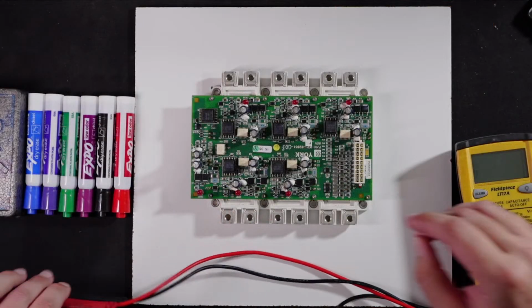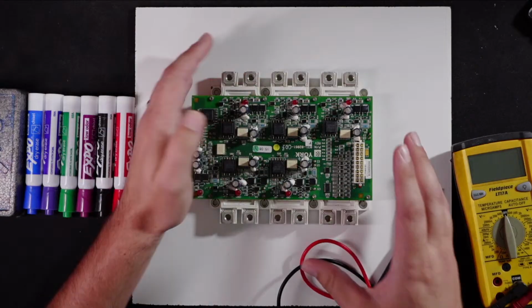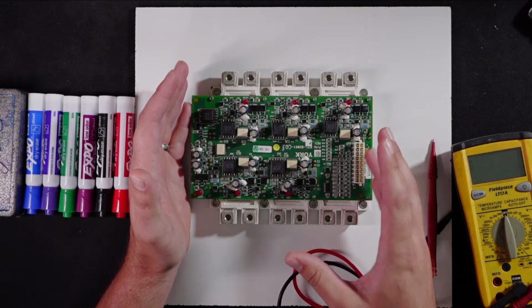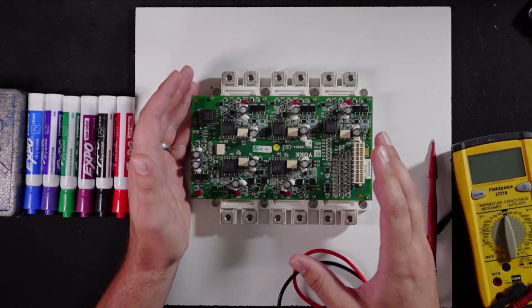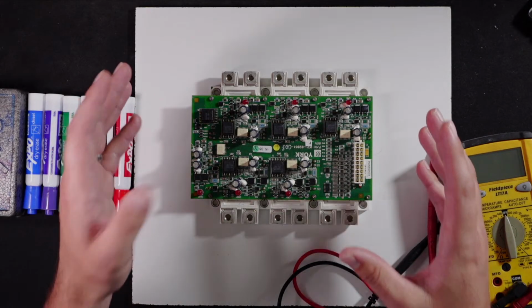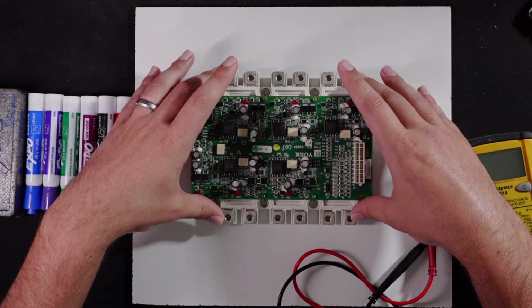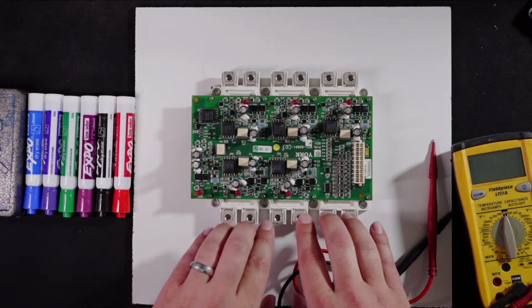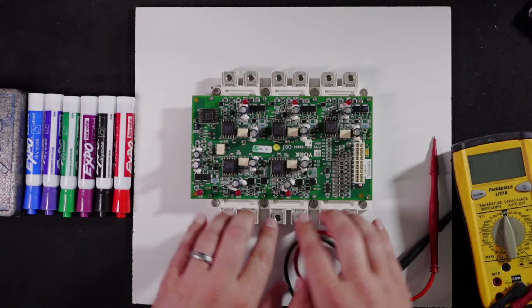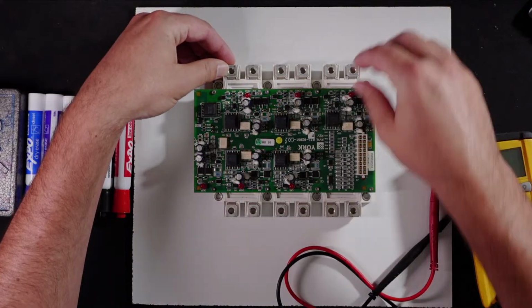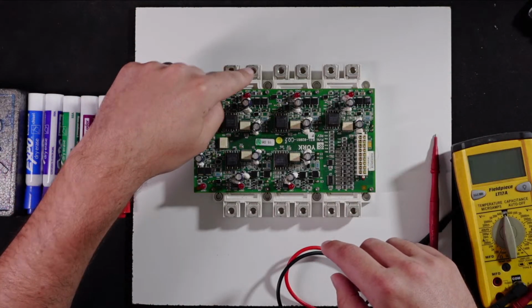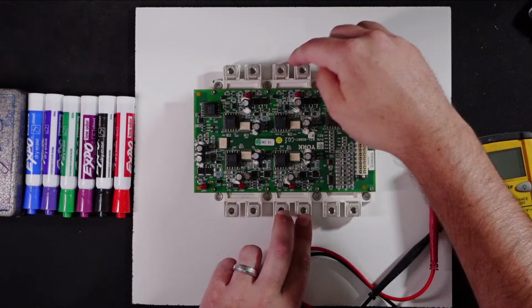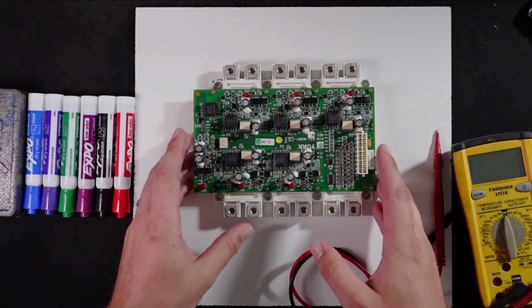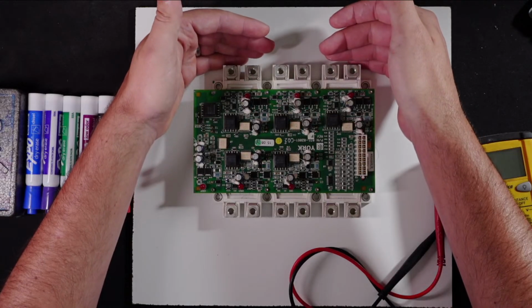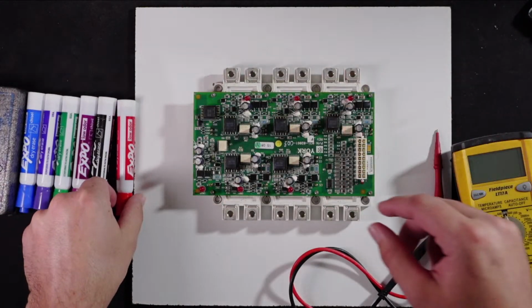So let's come over here. This is an IGBT. So let's start with some of the basics. This is an insulated gate bipolar transistor. In short, there's a set of diodes in here that control flow. What this device is doing is, make sure I get my orientation right, this is my DC bus side. So this would be my terminal 1, 2, and 3. And then these two are 1, 2, and 3, 1, 2, and 3. So DC power is coming in from this side, and then I am feeding AC out.